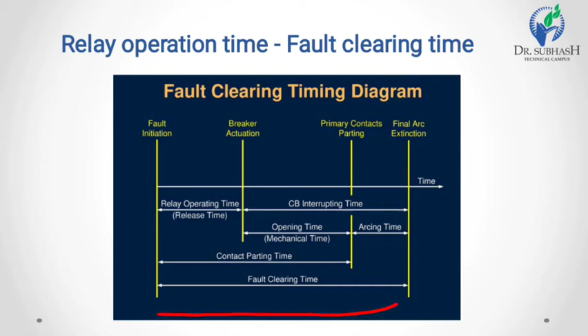After the relay operation, it will signal the trip coil and the CB will trip, separating the contacts, and the arc will extinguish. This time is calculated as the CB interrupting time. The time between the breaker actuation and the primary contact separation is called the mechanical time or opening time of the breaker. When the contact separates and the final arc is extinguished, that time is called arcing time. So from the initiation of the fault to the final arc extinction, this total time is called the fault clearing time. So we can measure the fault clearing time.